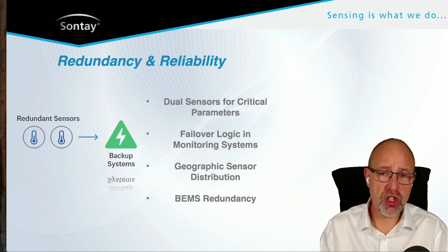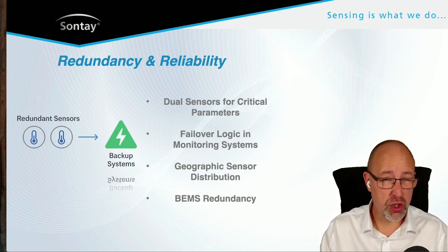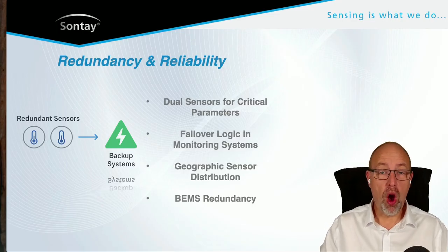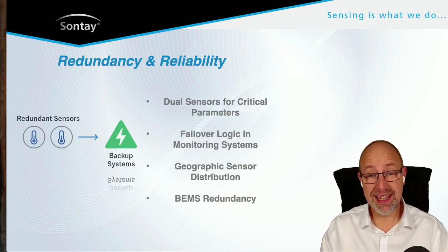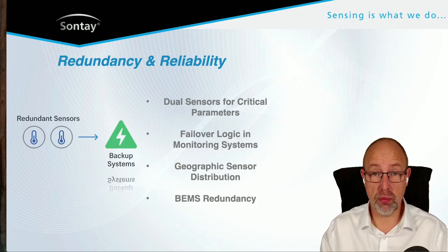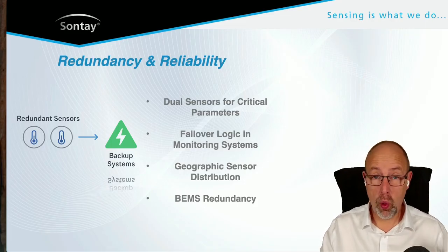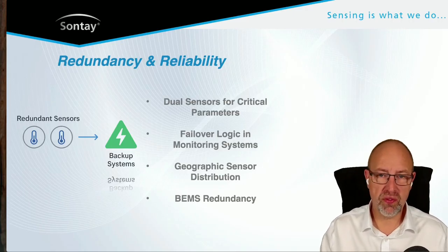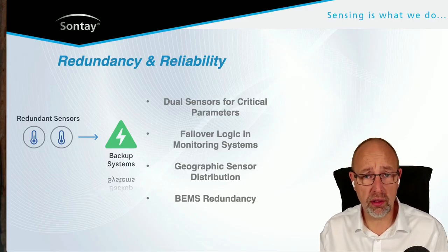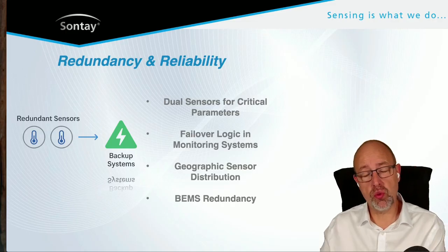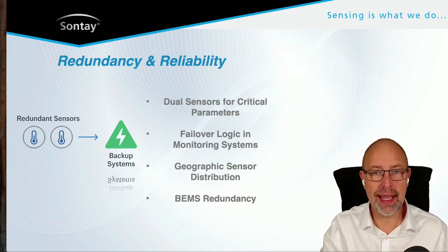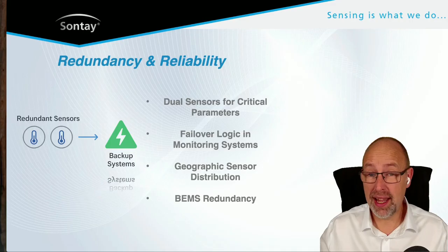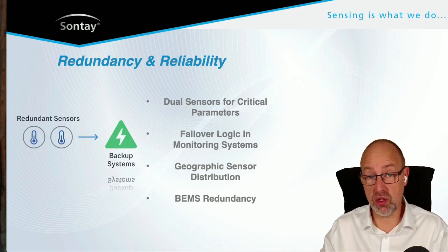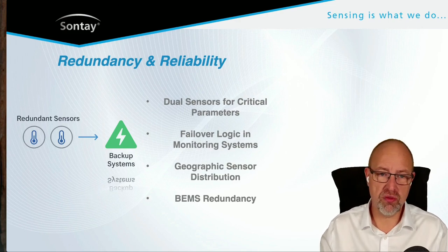In terms of monitoring solutions, failover logic is really important. What happens if a sensor fails? We need to know the operational parameters of a sensor. If one suddenly starts reading 150 degrees C or minus 50 degrees C, we know it's failed. We need logic in place to switch over to the redundant system and negate that sensor. And we need a really good alarm monitoring strategy so someone knows about it and can get that sensor replaced.